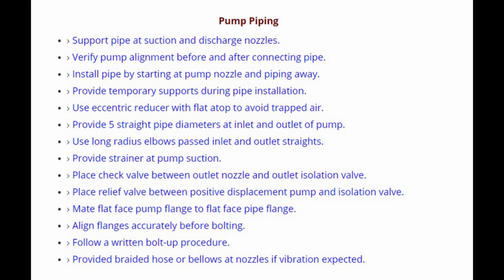Number 5. Use eccentric reducer with flat atop to avoid trapped air. Number 6. Provide 5 straight pipe diameters at inlet and outlet of pump. Number 7. Use long radius elbows past inlet and outlet straights.